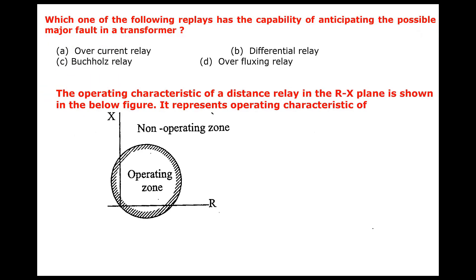Which one of the following relays has the capability of anticipating the possible major fault in the transformer? It is the relay that anticipates before the occurrence of the major fault. Buchholz relay is a relay that acts before the major fault because it detects slowly developing faults. So Buchholz relay anticipates the possible major fault in the transformer.